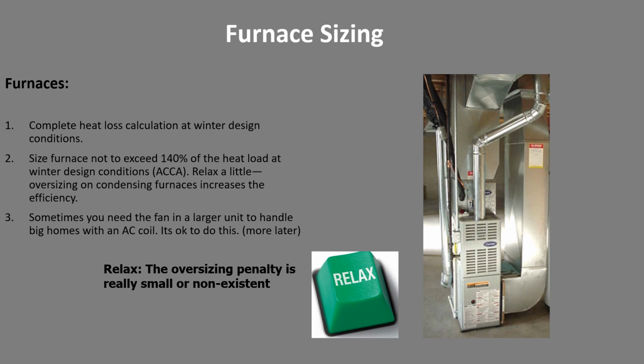Furnaces, ACCA says that we should not exceed 140% of the heat load of the house. That's really hard to do with new pieces of equipment in new homes. Typically, we're oversized by a factor of 2. It's probably not the biggest problem. By the time you start the oversizing by a factor of 3 or 4, it can certainly become a problem.